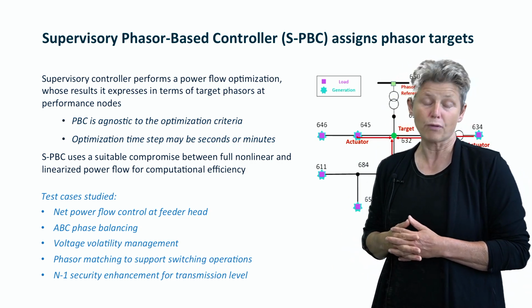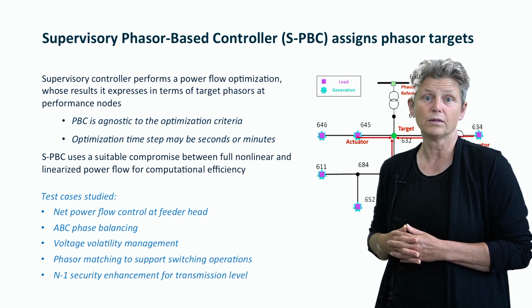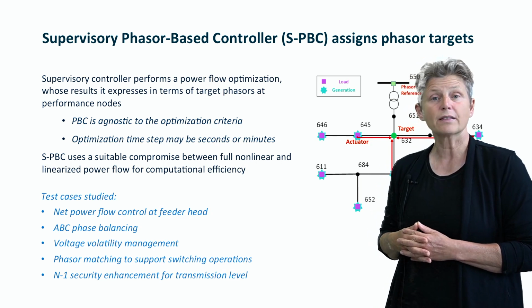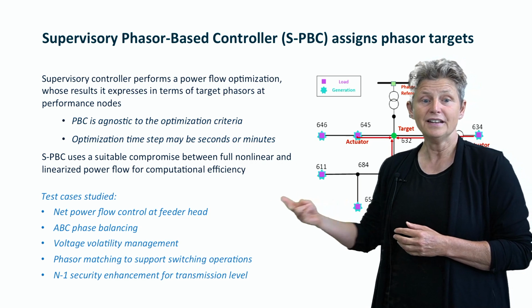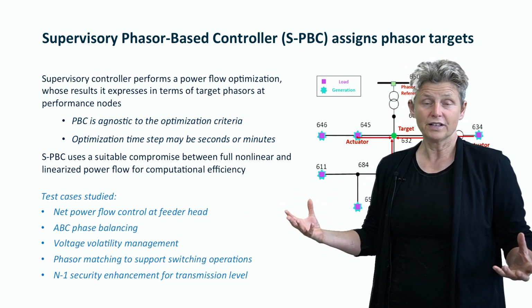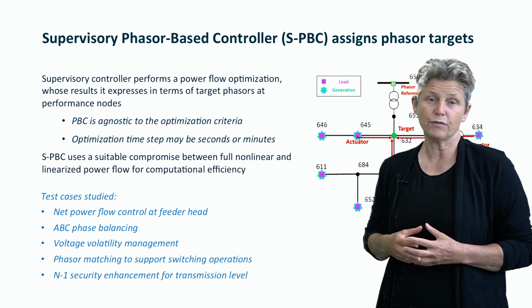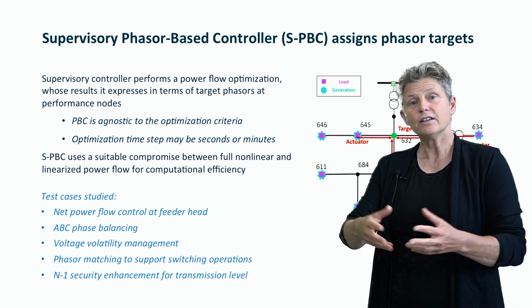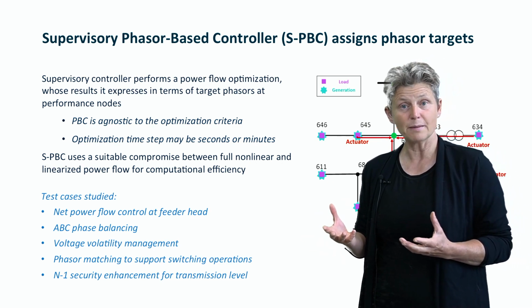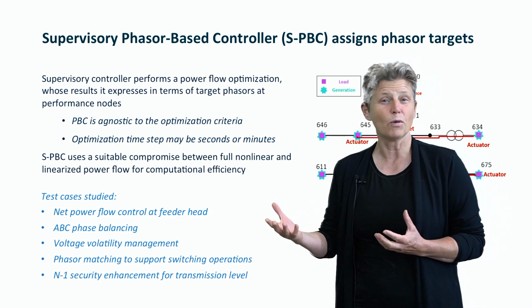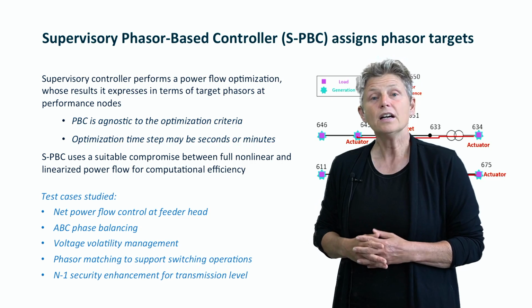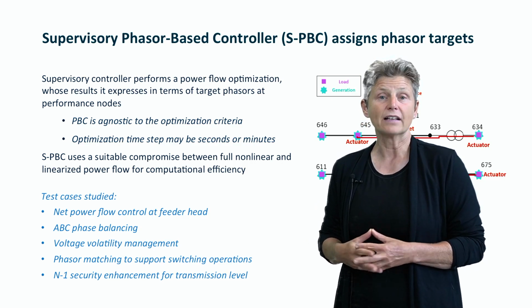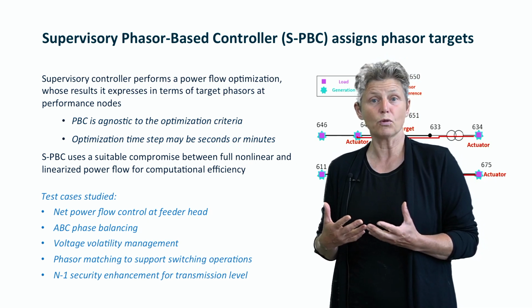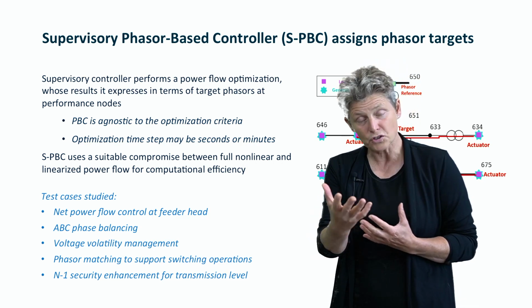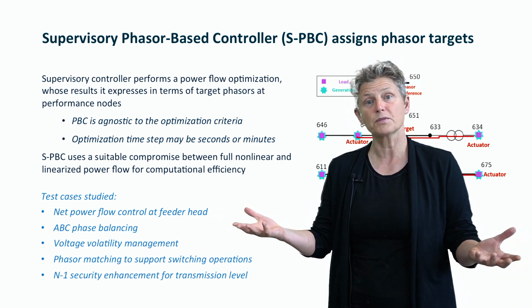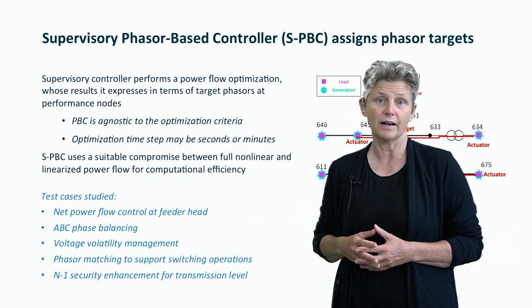Finally, a promising, I think economically viable, use case for phasor-based control is to look at the benefit to the transmission system of having net power flow control at the feeder head for multiple distribution circuits, and what that can save in terms of secure operations. A transmission level dispatch that might not be considered N-1 secure - meaning you couldn't do it because if any one item fails the lights would go out - if you have phasor-based control in place, that operating state may become acceptable or secure, because you can be confident that distributed resources from behind these substations will respond to a change in the grid operating state.